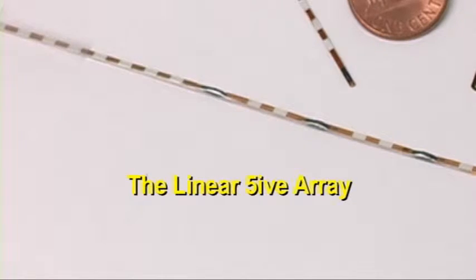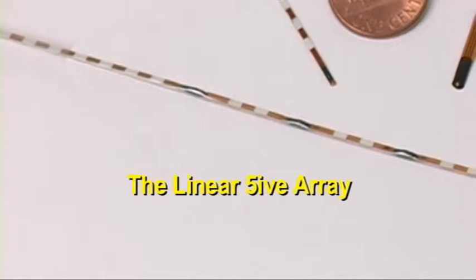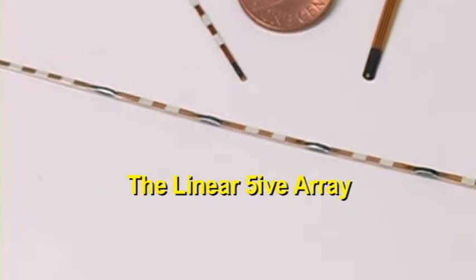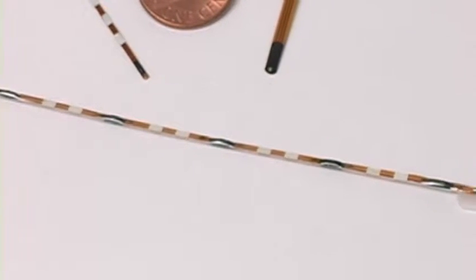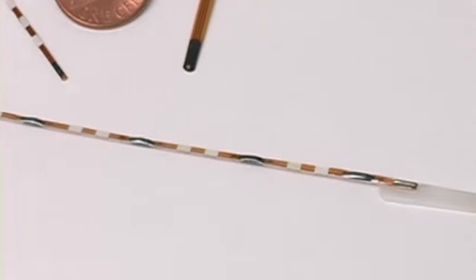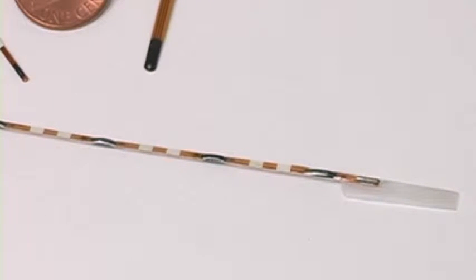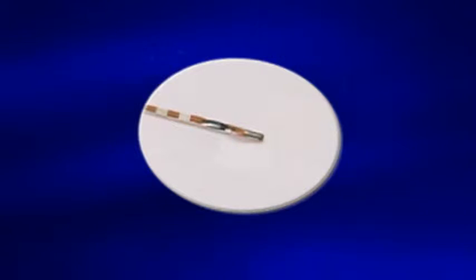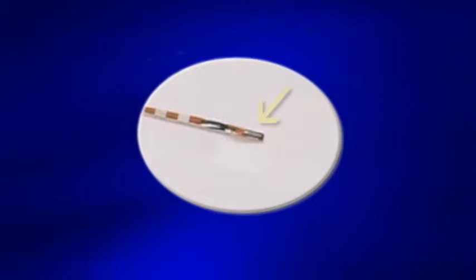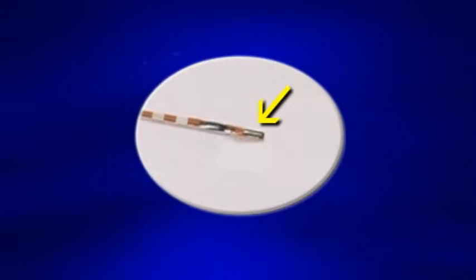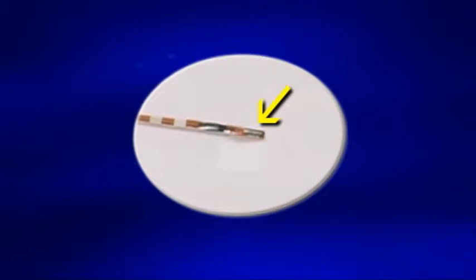The linear 5 array, with all 5 sensors on one flex, gives a dose profile. The array can be used effectively for direct measurement of intracavitary dose profiles during gynecological and prostate procedures. There is a radio-opaque marker on the end of the flex which will give a visual indication of the sensor's location in CT and X-ray images.